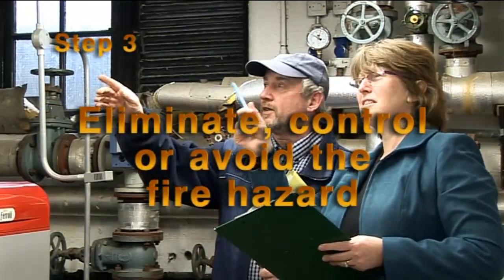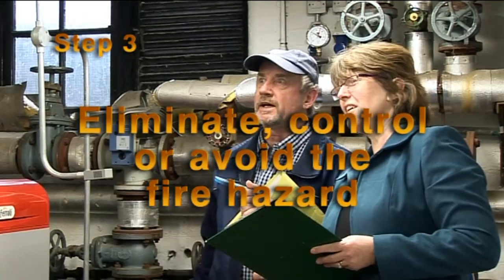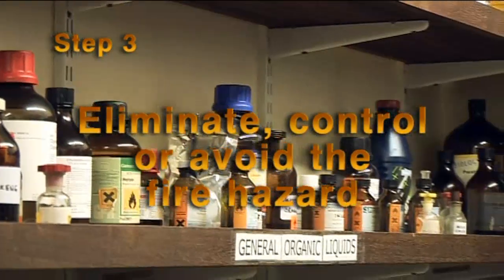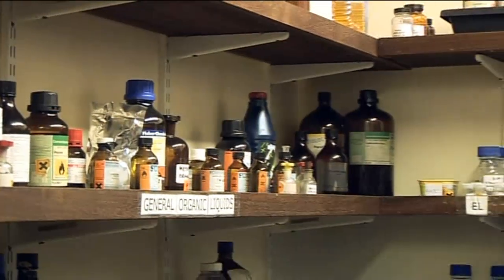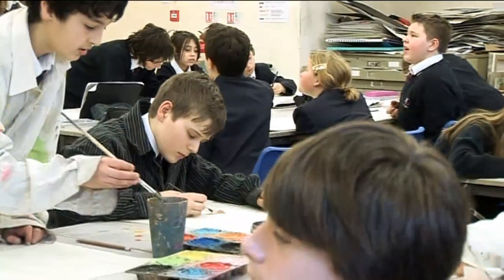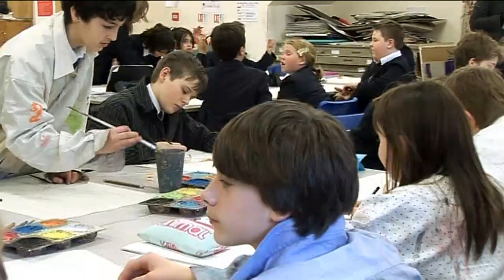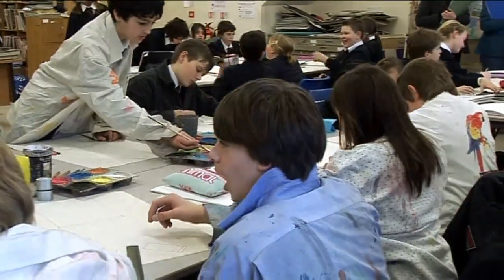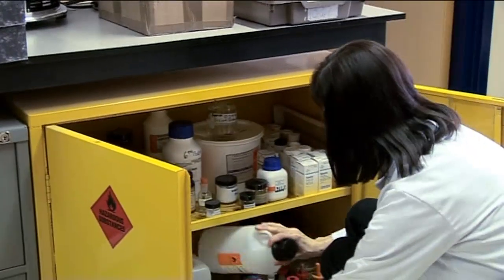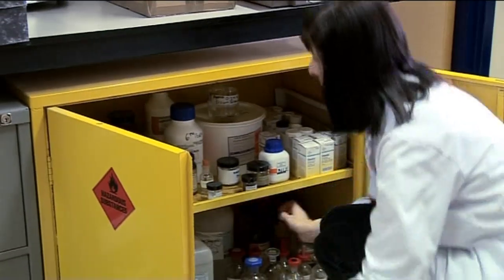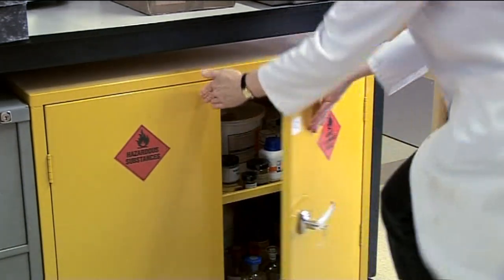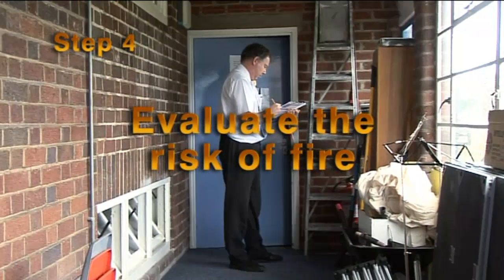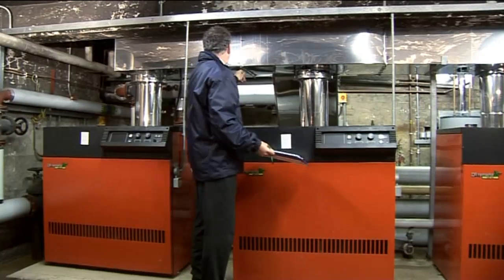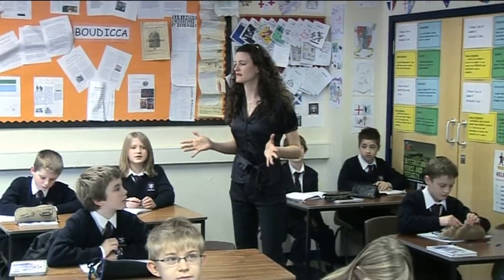Once hazards have been identified, steps need to be taken to eliminate, control, or avoid them. Wherever possible, materials that present a high risk should be replaced. For instance, solvent-based glues and paints could be replaced with water-based alternatives. If a material cannot be eliminated, then make sure that procedures are put in place to minimize the risk it represents. An evaluation of the risk of fire should then be made, identifying areas of high, normal, or low risk.